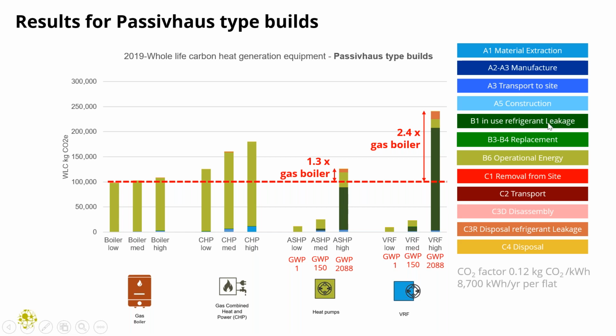And you can see the green part, it's mostly associated with the dark green part, which is B1, in-use refrigerant leakage. This was really important for us to find out because we would have a tendency to think, oh, heat pumps or VRF are always the way to go. But as we design ultra-low energy buildings, with a low demand and really good fabric and passive design measures, we have to be more careful about these things.